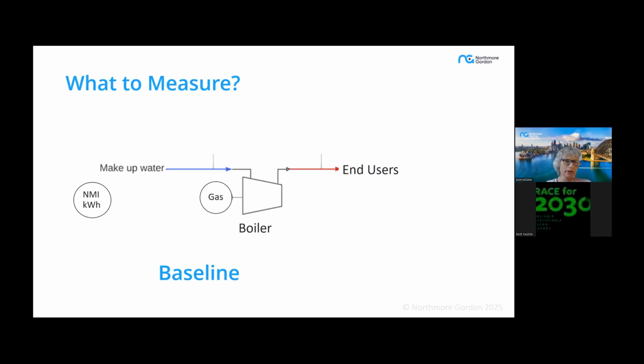The other thing that you need to be doing is understanding your electricity consumption before the implementation, because you're going to be replacing gas with electricity consumption. So if you don't have a good handle on your electricity consumption beforehand, you're not going to be able to show the difference, the change or the increase in electricity consumption for that comparison after implementation. And also you need to have available interval data for your site natural gas consumption. If your implementation is big enough to create certificates, you'll probably be able to get hold of interval data from your gas retailer, which is pretty straightforward to do.